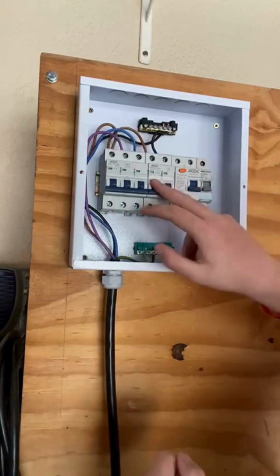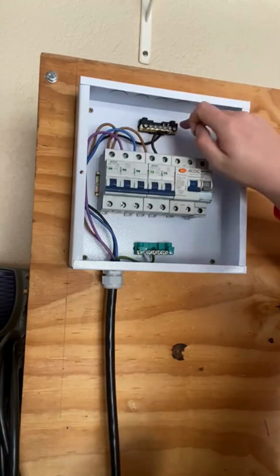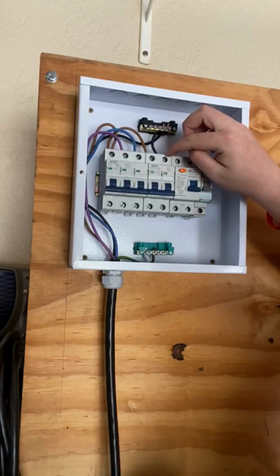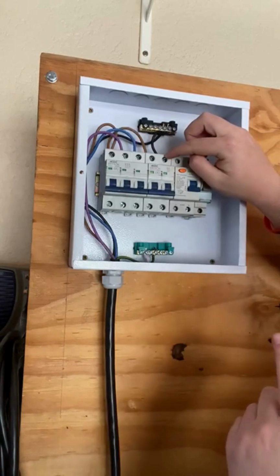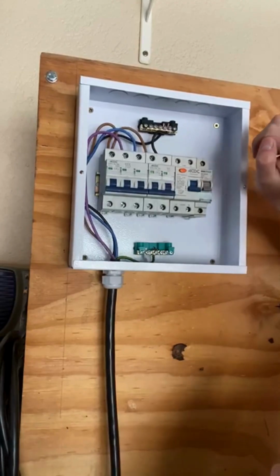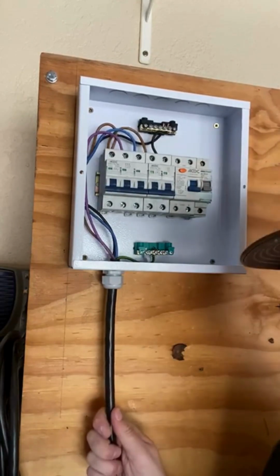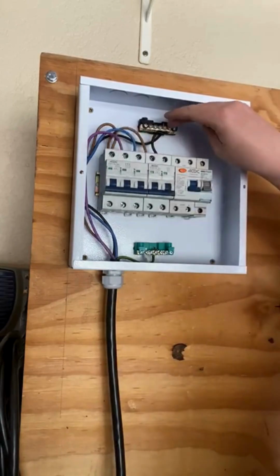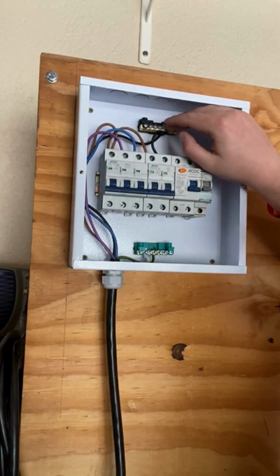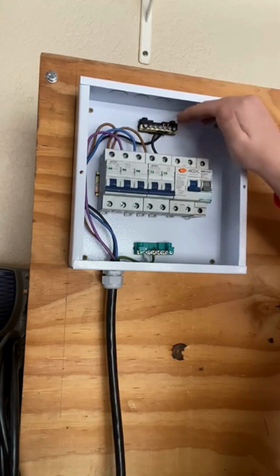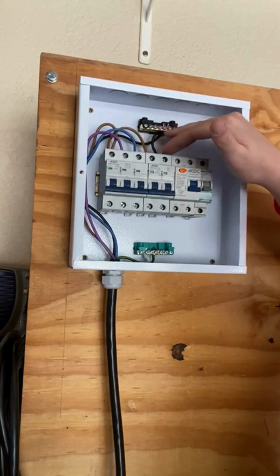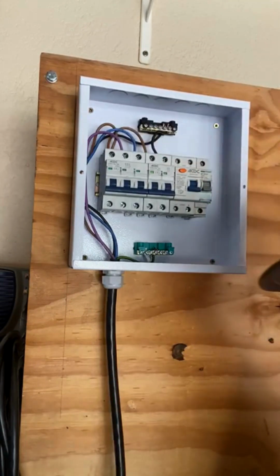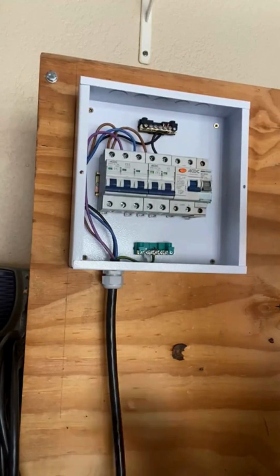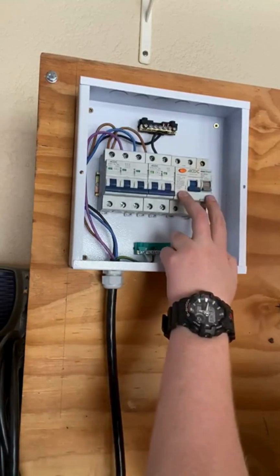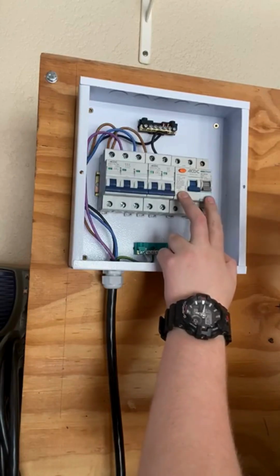Now you might be asking yourself, okay, what about the neutral? So the neutral, we've also connected to the neutral bus bar - the neutral connected to the single-phase isolator, we've just connected to the neutral bus bar. Why do we do that? Because the three-phase cable neutral is connected to the neutral bar, and then from the neutral bar, the neutral then feeds into the single-phase isolator. All right, and I did explain the ELCB and the circuit breaker.